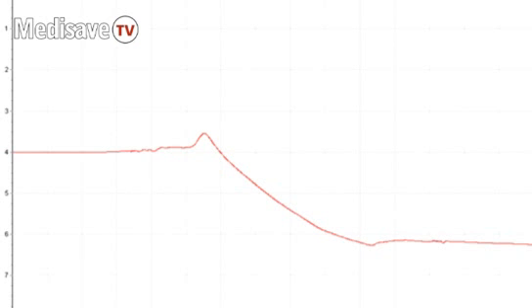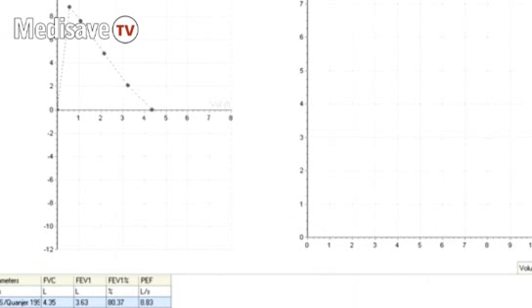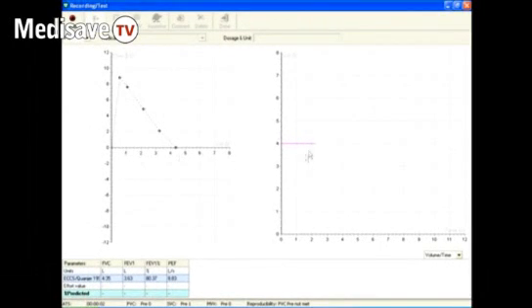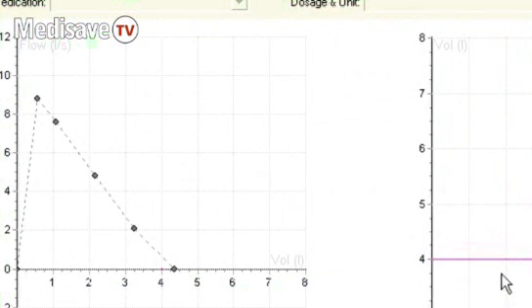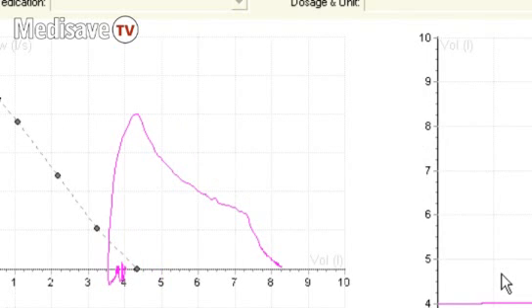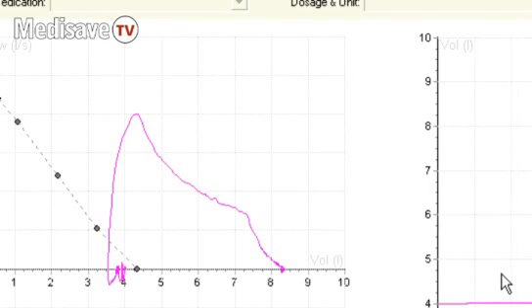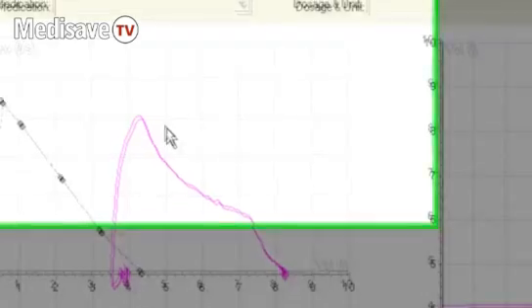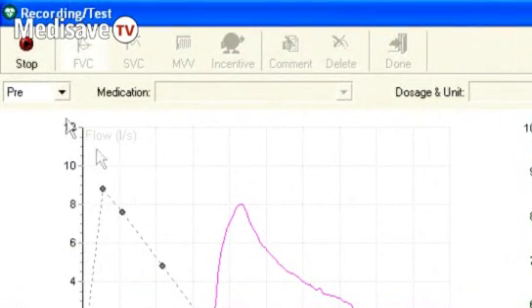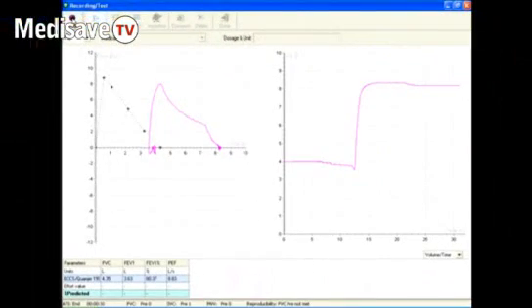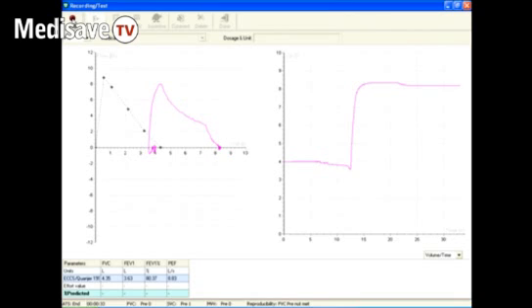If you're then ready to proceed to their forced vital capacity test, you click on that icon at the top of the screen. Then click on Record. When the screen tells you that it's ready to take the test, the patient can pick it up and this time blow as hard as they can for as long as they can. The blow is accurately measured on the PC screen and shown there. When they're finished, you press Stop.